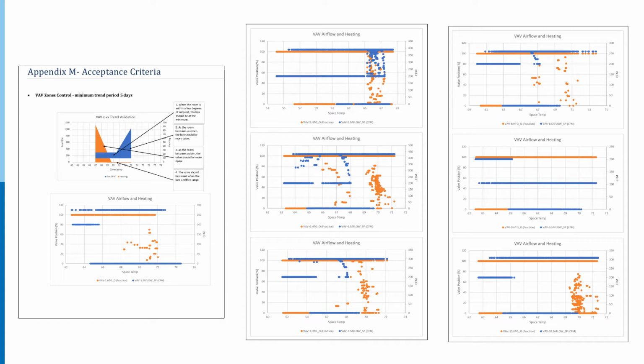Next thing I look at is the orange. That's the position of the heating valve. And first things first, the heating valve should be closed when the room is warm. So on the right side of the chart, the heating valve should be closed. And in this data, it's not. We are seeing heating valves that are fully open when rooms are above set point and should be calling for cooling.